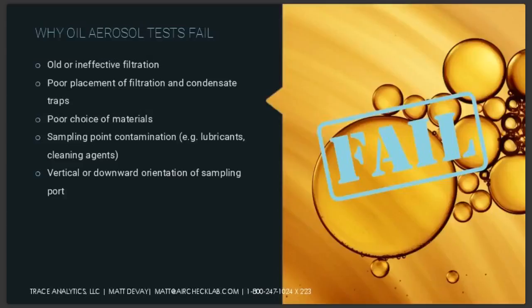Materials, if you're using a lot of polymer, oil aerosol loves to cling to polymers, and it becomes a point of continual low-level contamination. Just be careful with that kind of thing. Any devices that you have that may need to be lubricated, if you've got valves, certain gauges, certain measuring devices, quick releases that require lubrication, any of that kind of stuff, just make sure that you've got a way to clean that, because all of that stuff will end up in your aerosol analysis. And that same vertical or downward orientation of sampling port applies. You'll get that oil that will start to pool and collect in those areas. So avoid that prior to your point of use or sampling point.